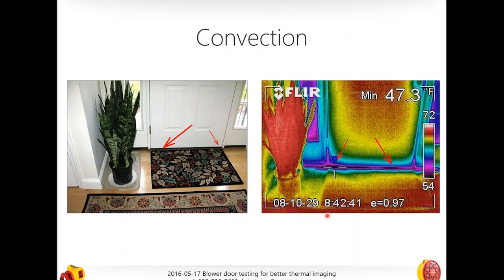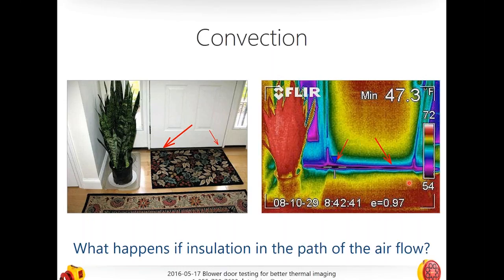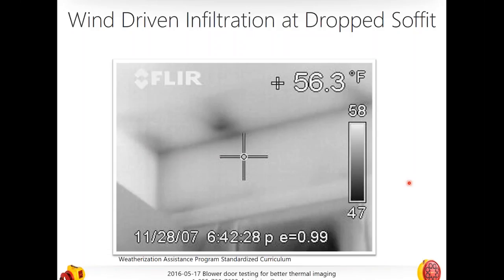Even if we're finding problems with conductive or convective heat loss, what the infrared imager is seeing is heat being radiated or emitted from a solid object — really important to understand. Here's an example of a mobile home before and after it was painted white with a reflective covering. You can see the big difference. For our purposes, though, we're going to talk about convective heat loss — that's where the blower door really meets the thermal imager and it can really help.